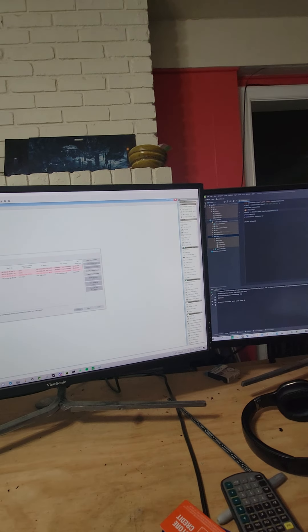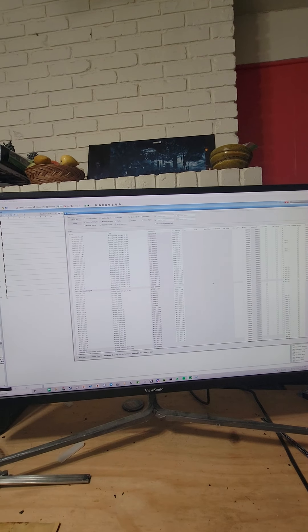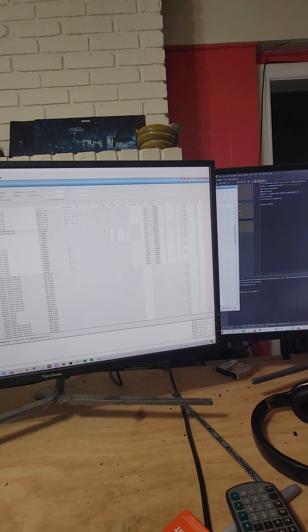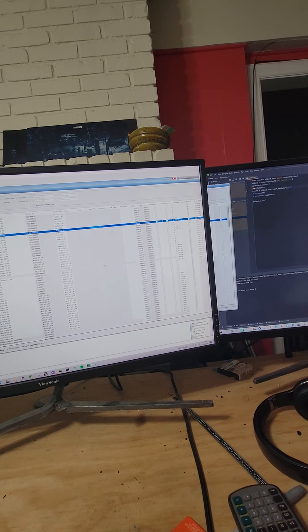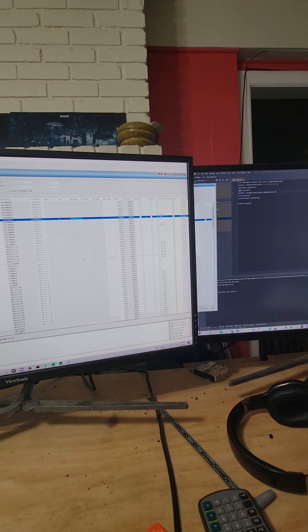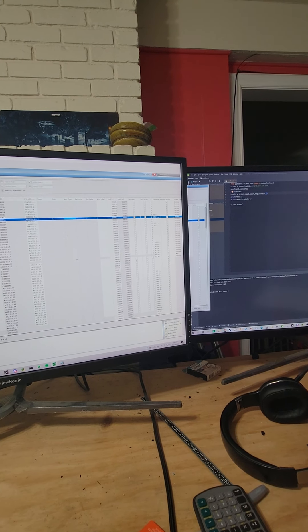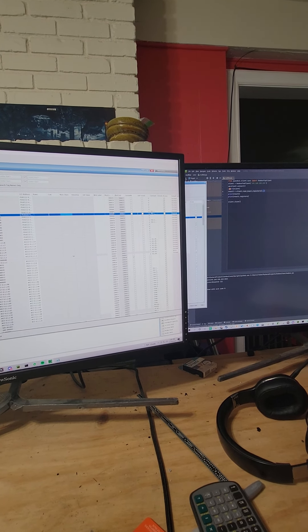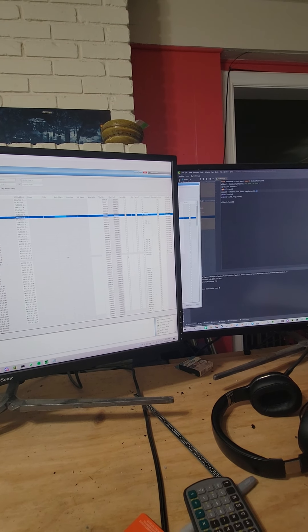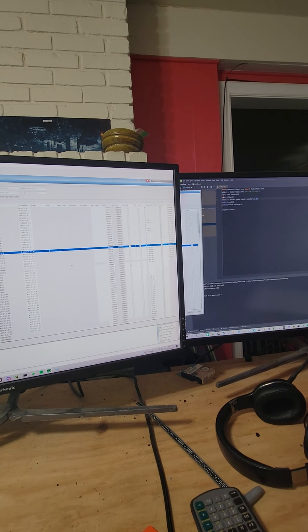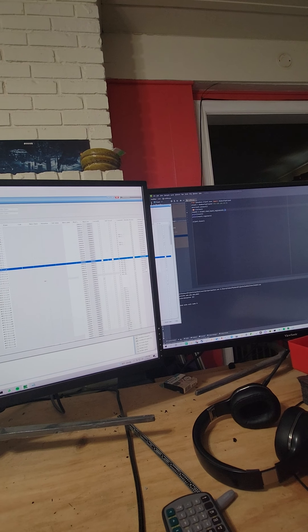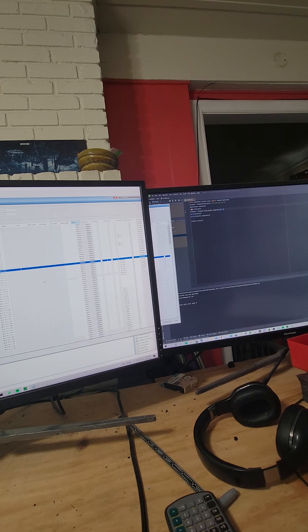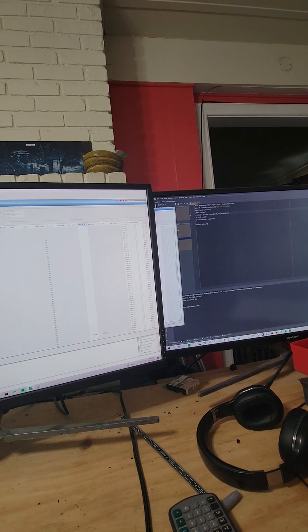So we go to the PLC and go to our tag database. This is very important. Inside of here, whenever we have tags, they're not automatically going to have Modbus labels associated with them. You have to populate these. And it's very important that you then runtime transfer or stop transfer the Modbus labels over to the PLC. If you don't do that, it's not going to work. You're going to just pull zeros the entire time. I did that earlier. That was a several hour learning experience.